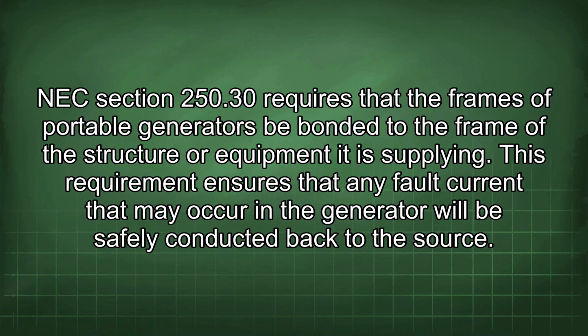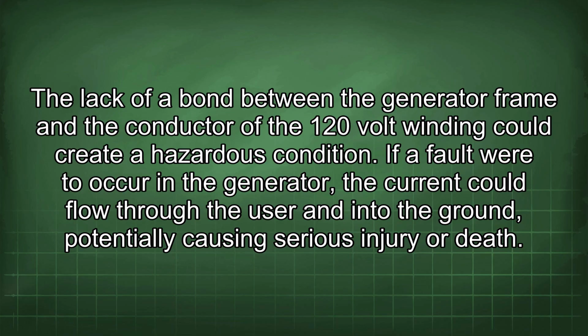NEC section 250.30 requires that the frames of portable generators be bonded to the frame of the structure or equipment it is supplying. This requirement ensures that any fault current that may occur in the generator will be safely conducted back to the source. The lack of a bond between the generator frame and the conductor of the 120-volt winding could create a hazardous condition.